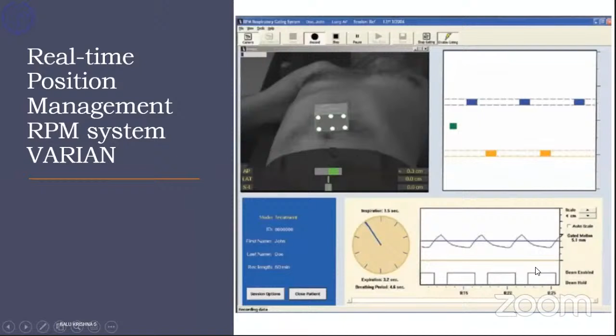So while the patient is on the couch with this transducer on the abdomen, the respiratory cycle will be mapped on the monitor. So this is how it would be mapped. I have shown real images earlier in one of the slides. And once that is mapped, the system also connects to the imager or the treatment machine. And it can actually send inputs to the imaging machine to say when to image and when the imaging beam has to be switched off. So on and off is triggered by the respiratory motion. So it is actually a respiratory-controlled beam on, beam off. Same thing in the linear accelerator also.